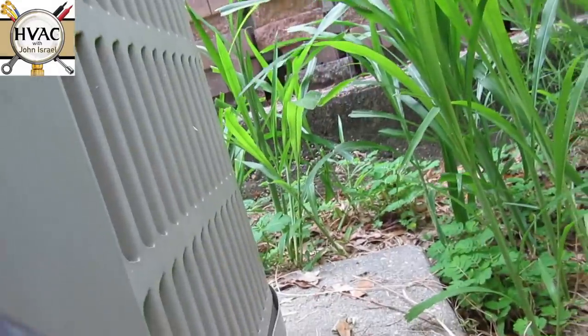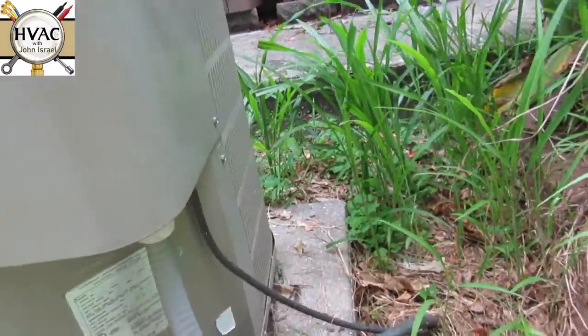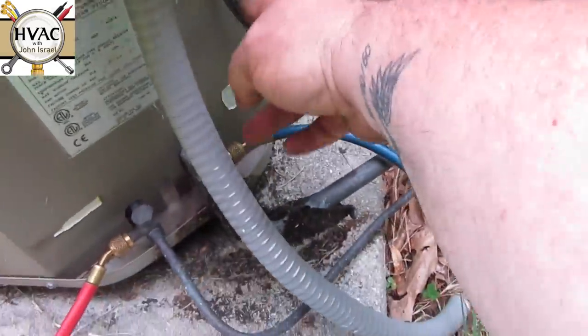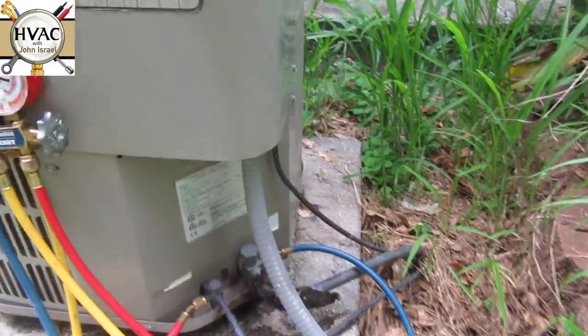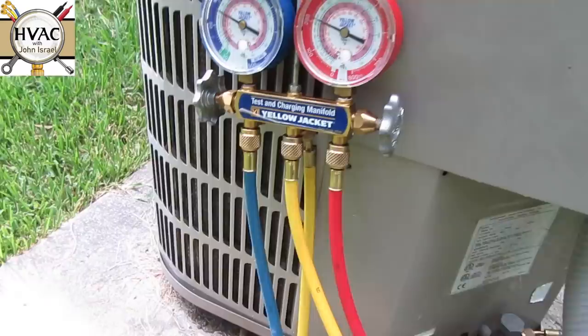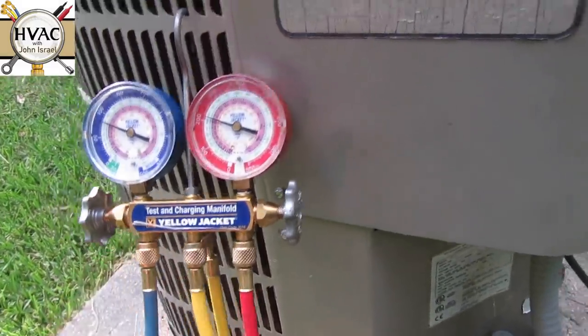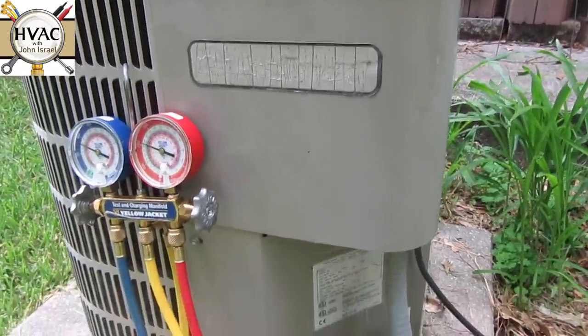Now that the strip heat is not running with the air, it's cooling well. There's the disconnect way over there. The condenser's out in the yard and the lines go underground — so does the high voltage. Wait — that's copper. That's rigid copper going — oh, that's for the low voltage. There's the whip. Looks like they put the low voltage line in some copper pipe with a connector — that's a new one on me. I've never seen copper pipe used as conduit. Suction pressure's coming down to about 80, so we're okay.